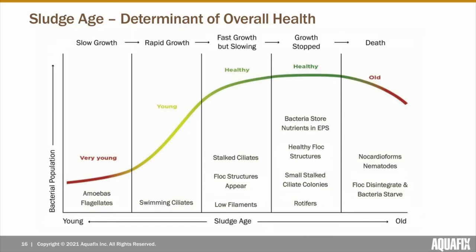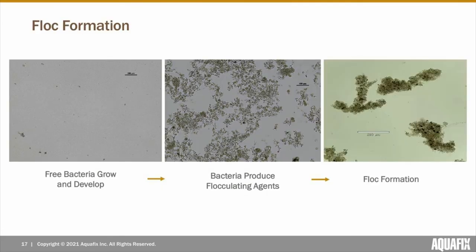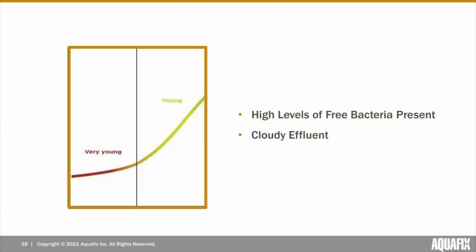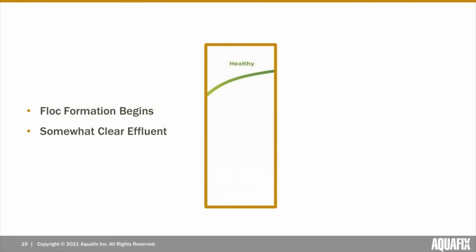Flock formation occurs when free bacteria grow and develop while consuming nutrients. Then, under ideal conditions, bacteria will begin to produce and secrete flocculating agents, mainly extracellular polymeric substances or EPS. These flocculating agents allow bacteria to stick together and form floc. At a younger sludge age, high levels of free bacteria will be present, resulting in low settling and a cloudier effluent, because bacteria need adequate retention time for floc formation to occur. As sludge age becomes older, floc begins to form as free bacteria reduce nutrients and flocculating agents.